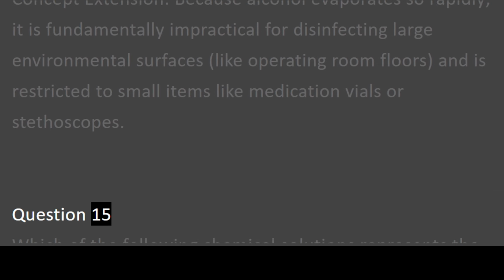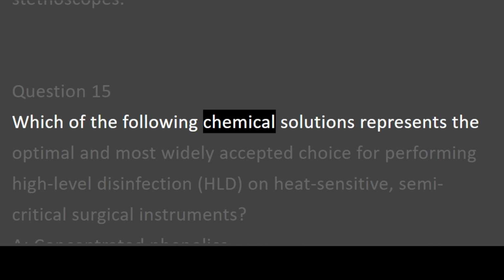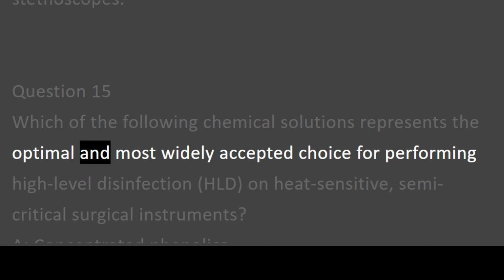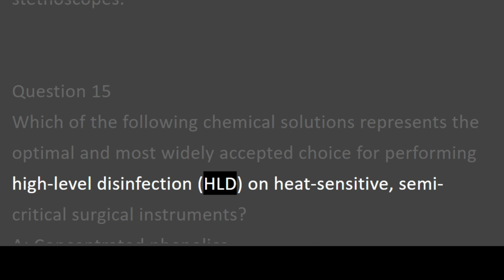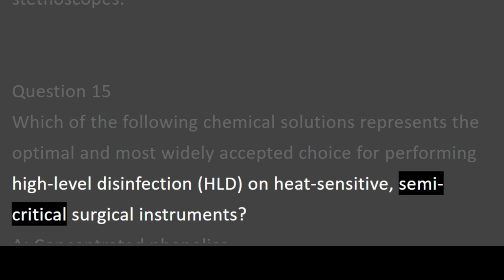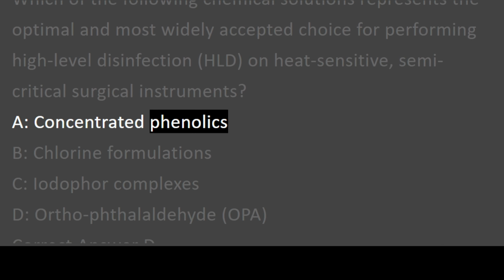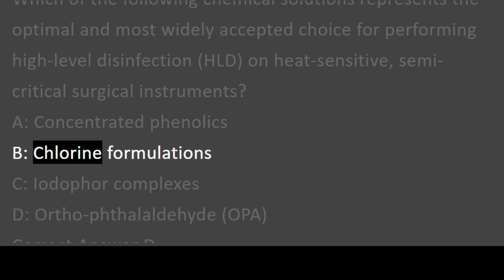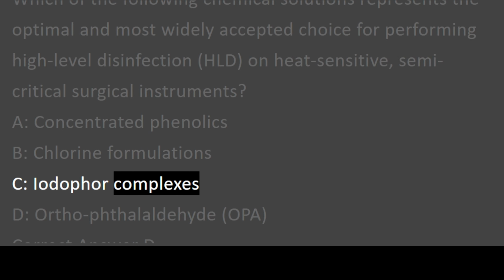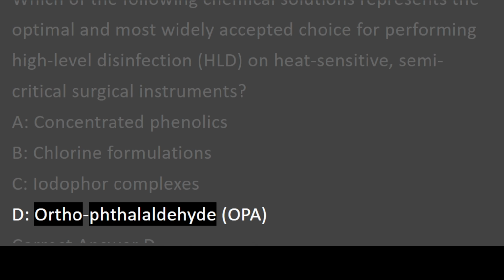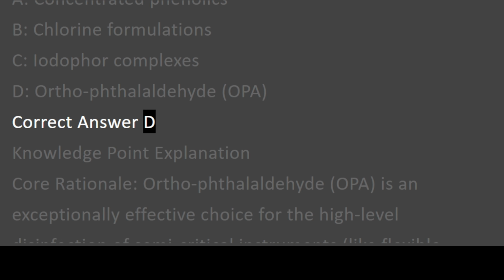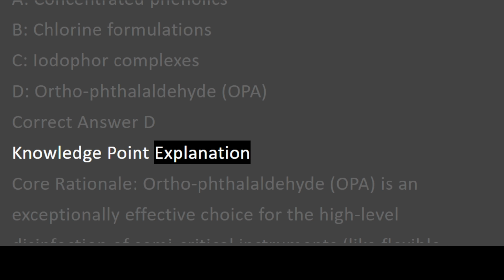Question 15. Which of the following chemical solutions represents the optimal and most widely accepted choice for performing high-level disinfection, HLD, on heat-sensitive, semi-critical surgical instruments? A. Concentrated phenolics. B. Chlorine formulations. C. Iodophor complexes. D. Orthophthalaldehyde, OPA. Correct answer D.